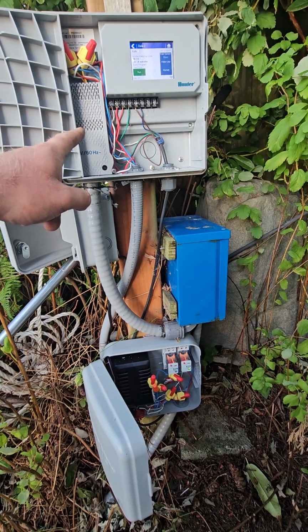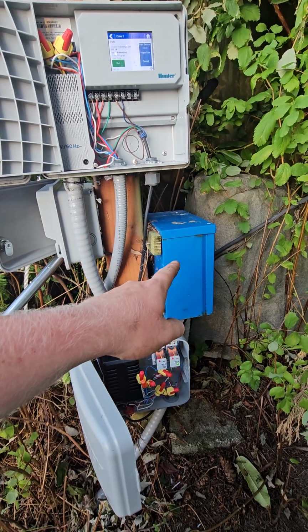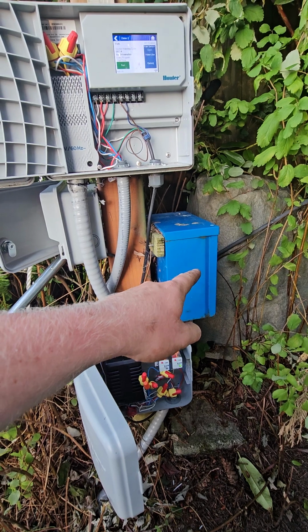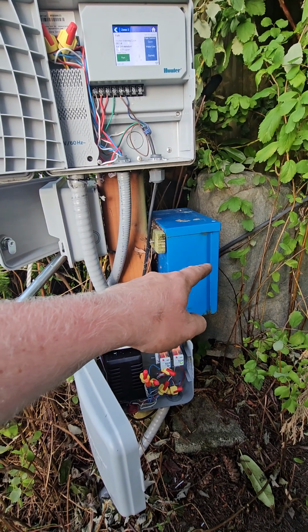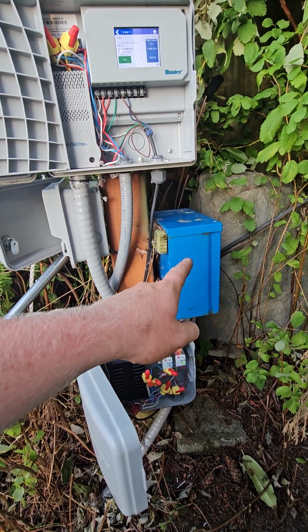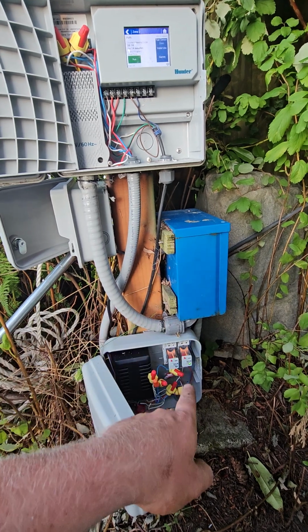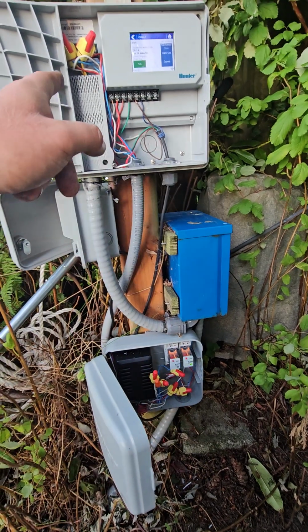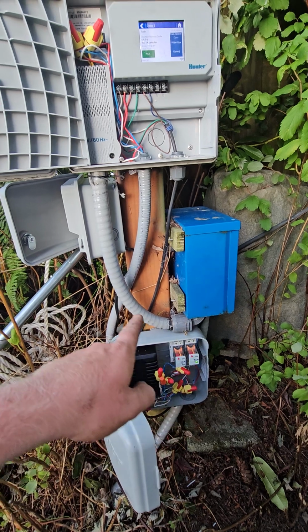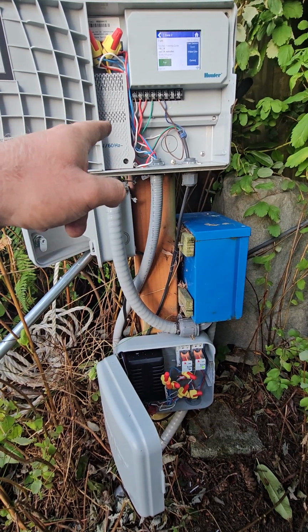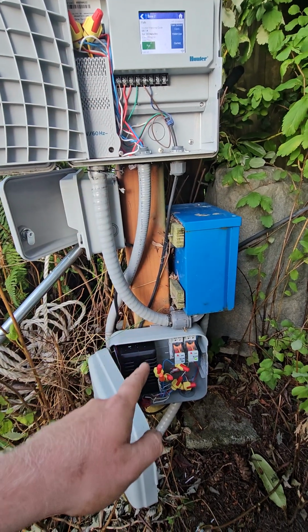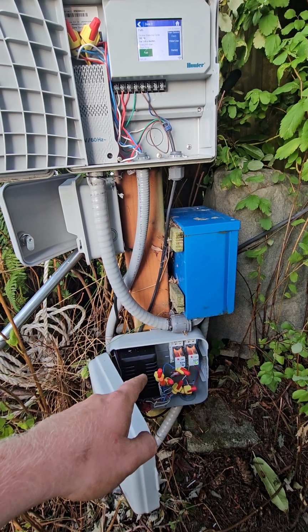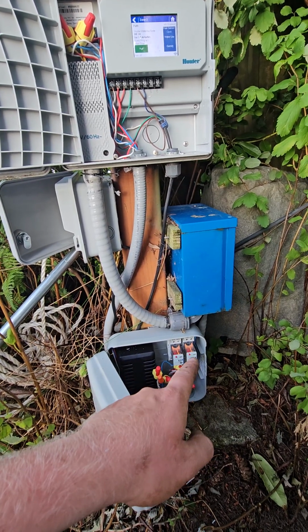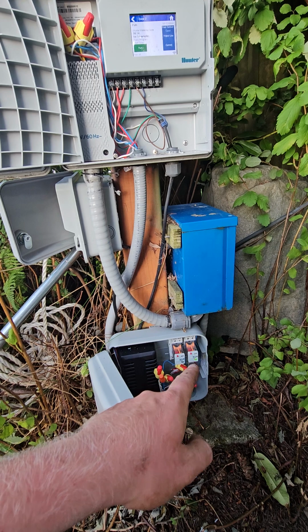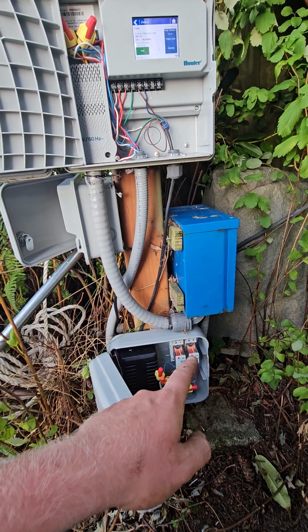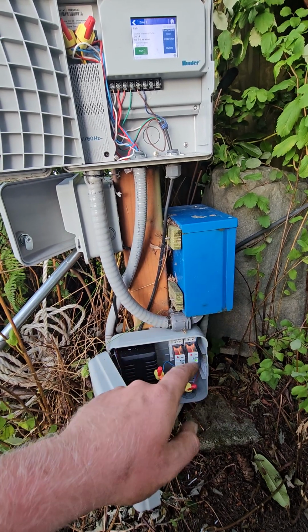So the transformer's here, the power for it comes into here. So we have the line voltage at 120 volts splits off, and there's a fuse in there. It's a glass fast blow fuse. And so we have this on the 24 volts output of that transformer too. The way this goes is 115 volts comes through here, goes through a transformer, and then it's wired off, and immediately goes back down into the UPS on the input side. So on that input side is where we have this relay. And now what this relay does is that it keeps the circuit open, and then if it loses power, so if we blow that fuse, it drops power.